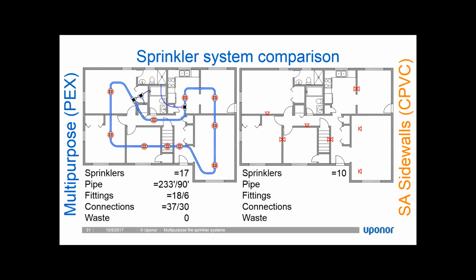Usually it does increase the amount of sprinklers just because you're dealing with corners and basically sprinklers that spray in one direction. And I want to point out that in the lower right-hand corner, I have the sidewalls kind of out in the middle of the room, and there's a reason for that. I'll get to that. So it looks weird right now. When I start adding pipe to this, I'm going to rise up in the wall, and then I use a special sprinkler fitting that's back-to-back. So I'm just using a couple threads, and I haven't included those threads on the connections. So the amount of connections so far looks like a lot fewer connections than when we were doing the standalone system using all pendant sprinklers.